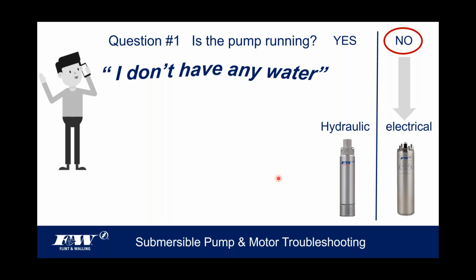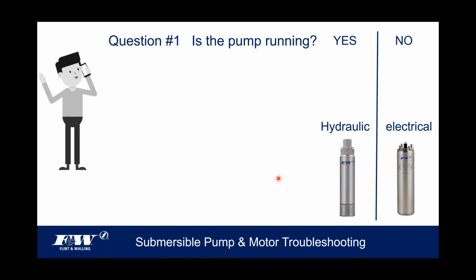And so when they tell me that the pump is not running, my mind at least is going to start focusing on, okay, well, maybe there's an issue with the motor, maybe there's an issue with power to the motor, whatever, but it's going to land more on the motor side than on the hydraulic side. All right, so what if they say yes? The pump is running. Well, if they say the pump's running, it tells me the motor's running, right? Again, these are some very upfront, very basic fundamental questions. It tells me the motor's running.